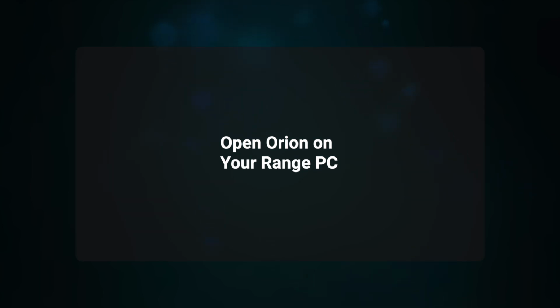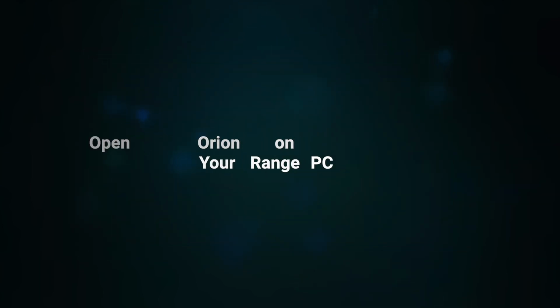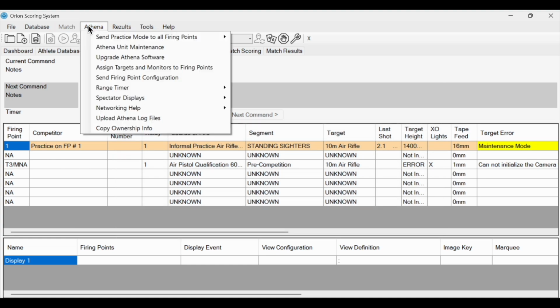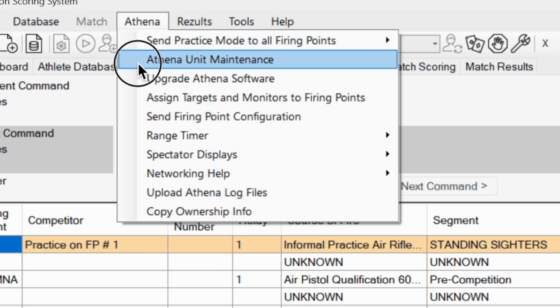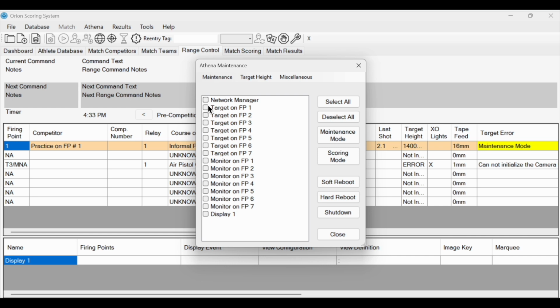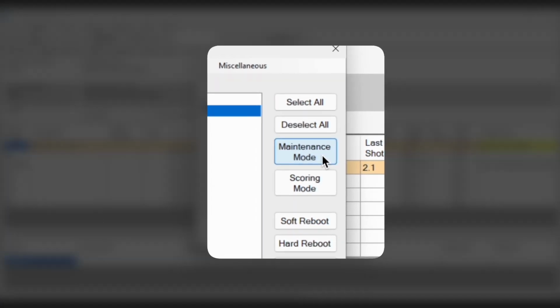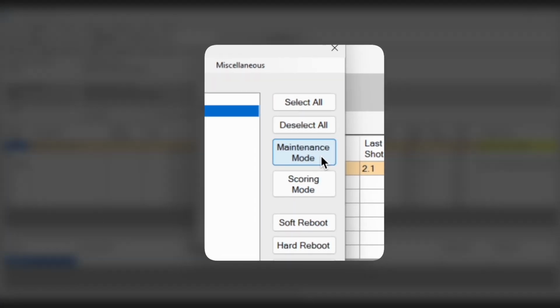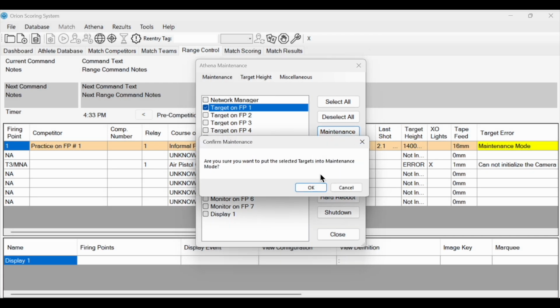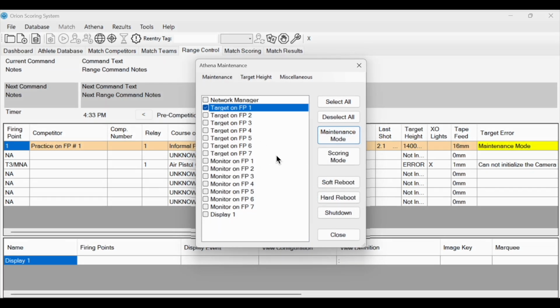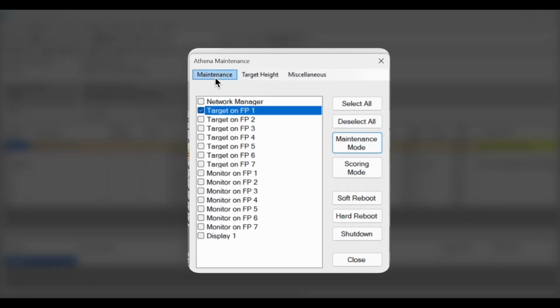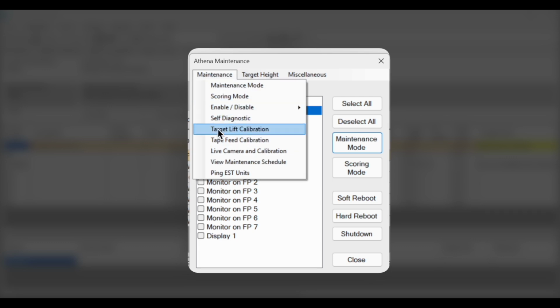To start, open Orion on your Range PC. To begin the target lift calibration, select Athena from the menu bar, then Athena Unit Maintenance. The Maintenance dialog box will open. Before continuing, make sure you enable maintenance mode on the target. From here, select, or tick, the target that needs calibration. Once selected, select Target Lift Calibration from the Maintenance drop-down menu, as shown.